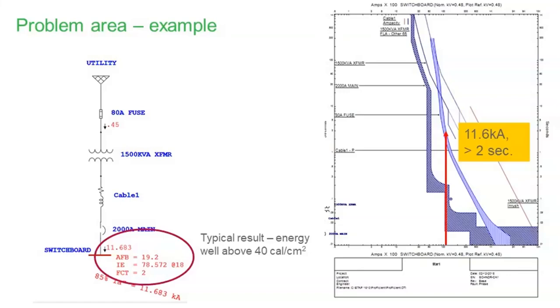One example problem area will let me highlight one more thing before we get into the solution categories. I've got a simple system here, utility source on the left-hand side, a 1500 kVA transformer, giving service to a service entrance switchboard down there at the bottom at 480 volts. And I've just run the numbers there. Incident energy, 78.57 calories per centimeter squared. It's almost 80 calories per centimeter squared there at the service entrance. And why is that? Because my protection there is the fuse on the primary side of the transformer. That FCT there at the bottom, the fault clearing time, 2 seconds.